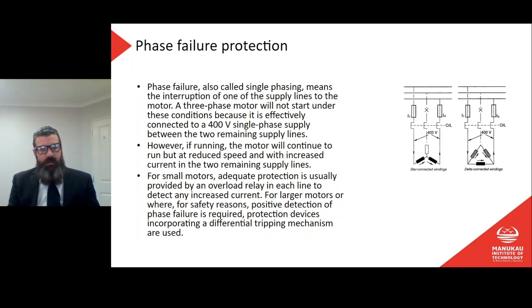For small motors, adequate protection is usually provided by an overload relay in each line to detect any increased current. For larger motors, or where for safety reasons positive detection of phase failure is required, protection devices incorporating a differential tripping mechanism are used. Right, so that's telling us, as in the previous slide, that most motors will have an overload on the contactor itself, and that overload, in most cases, will give us enough protection. So if we lose a phase, then we're going to get a high current in the other two phases. As I said, it will keep running on two phases, but at significantly higher current. That high current will then be, in most cases, enough to trip that overload.